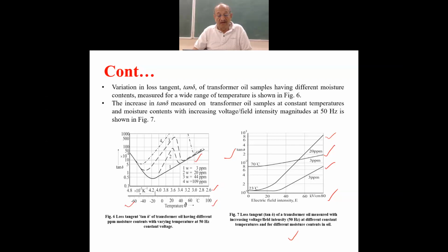So at such high voltages of something like 15 kV, absolute value of the voltage, there may be partial breakdown phenomenon in the setup. So the guard ring capacitor is developed in such a way that no partial breakdown phenomenon takes place when you conduct the experiment with the standard test cell or guard ring capacitor.